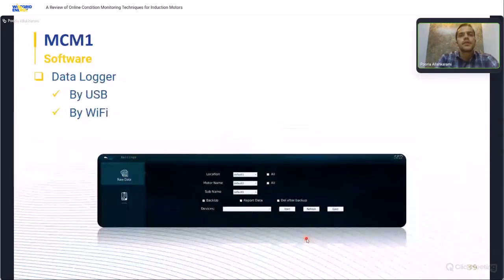And also the reports of the motor can be stored on the device storage and extracted without any external software. The device creates a local Wi-Fi, and all you need to do is enter the IP address of the device into the browser on your mobile or laptop and extract the information. Also, a USB port on the device allows you to transfer the data via flash drive. This USB port can be used for firmware updates with the dedicated file.